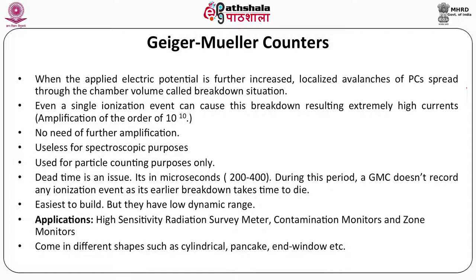The same pulse height is achieved for any kind of radiation, so GM counters are used for particle counting only. The resolving time or dead time is very high — between 200 to 400 microseconds — during which the GM counter does not record any ionization event. But it is the easiest among all three types to build and has high sensitivity, so it can detect even a small amount of radiation. GM counters are used in high-sensitivity radiation survey meters where low levels of radiation are expected, and for contamination monitors and zone monitors. They come in cylindrical, pancake, and end-window shapes depending on the application.